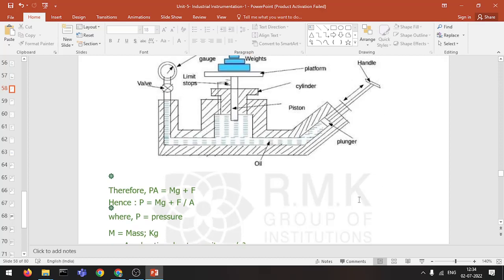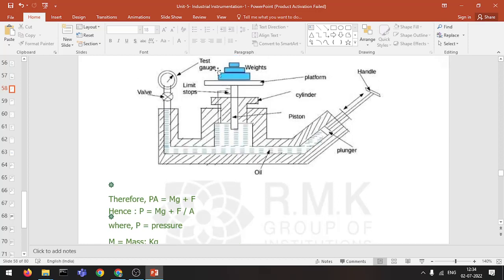Now you have already calculated P. The pressure gauge which is to be calibrated is connected over here. The same known weight which is used to calculate P is placed on the platform. Due to the weight, the piston moves downwards and exerts a pressure on the fluid. Now the valve in the apparatus is opened so that the fluid pressure P is transmitted to the gauge, which makes the gauge indicate a pressure value.